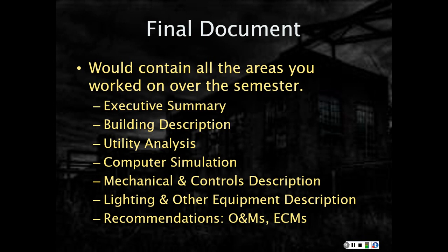Then you'd have the recommendation area, O&Ms first typically, and then ECMs or ECOs, in order of their simple payback, shortest to longest. Now remember, the O&Ms and ECMs would be listed individually, calculated first, and then combined effects, typically separate, and noted as such.